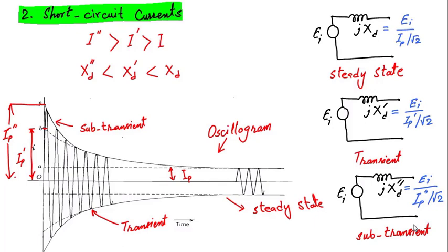The main power transformer must also be capable of withstanding this current, because such a large value of sub-transient current will produce very strong magnetic forces inside the transformer, so it may displace the windings inside the transformer or even in the generator. So these are the design requirements: the generator, transformer and all the equipment which will carry this current must be capable of withstanding it. Similarly, circuit breakers are designed to withstand this very high initial sub-transient current.